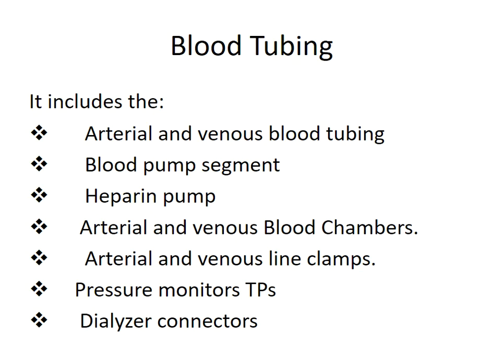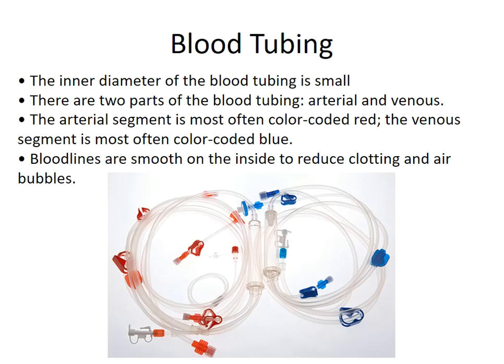The blood tubing includes the arterial and venous blood tubing, the blood pump segment, heparin pump, arterial and venous blood chambers, arterial and venous line clamps, pressure monitors, transducer protectors, and dialyzer connectors. The arterial segment is color-coded red and the venous segment is color-coded blue. The inner diameter of the blood tubing is small, and the blood tube should be smooth on the inside to reduce clotting and air bubbles.